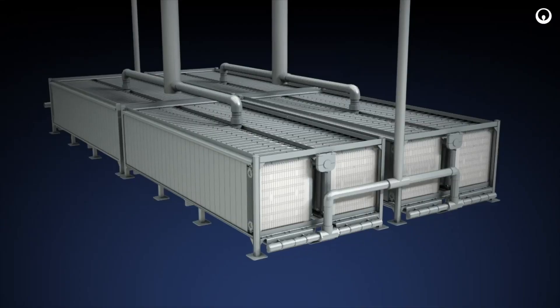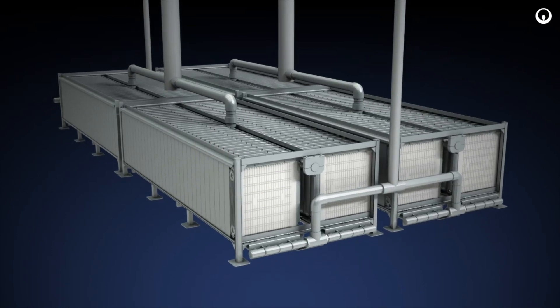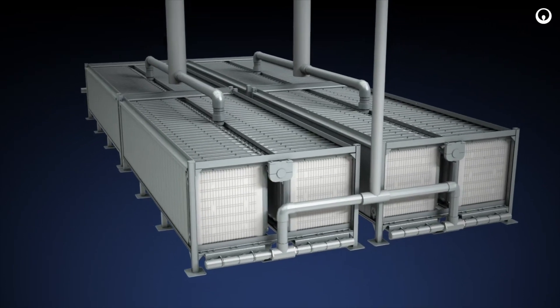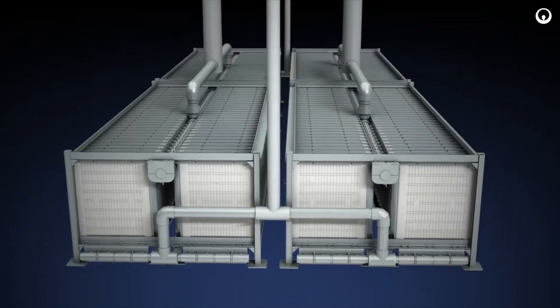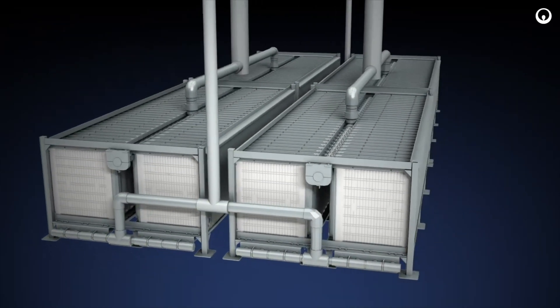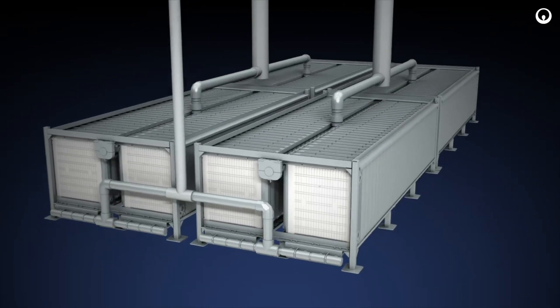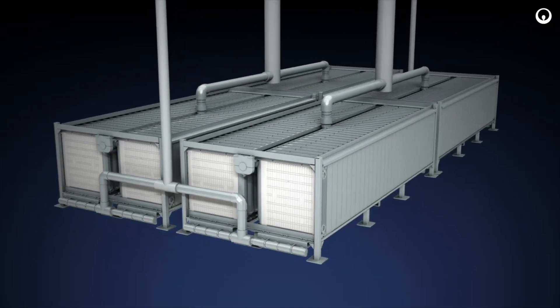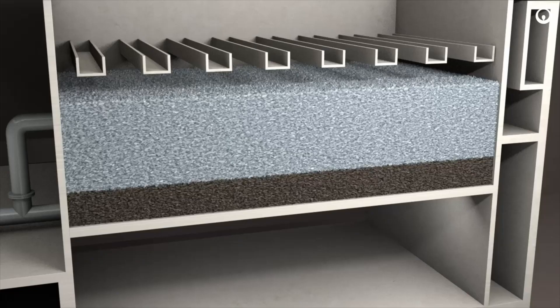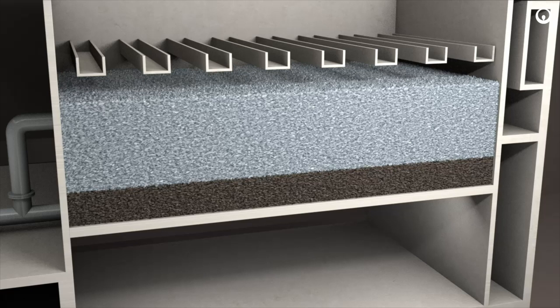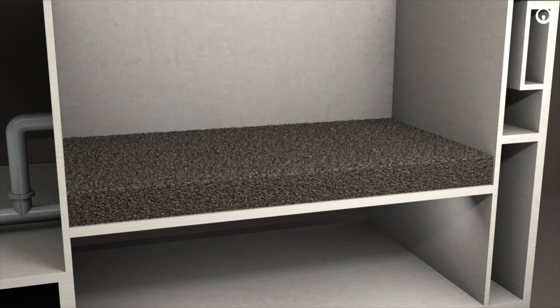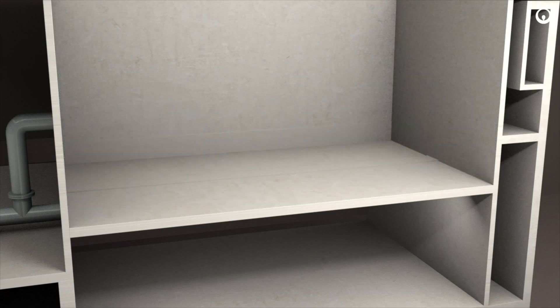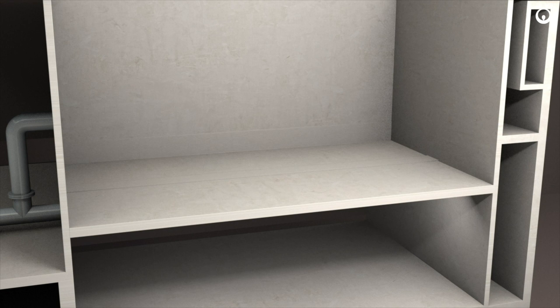Through simple modifications, Veolia makes converting an existing media filter to MGF fast and easy. The inside of the media filter requires a few simple modifications. First, the backwash overflow troughs and the media in the filter are removed. Holes are cored in the bottom of the tank.